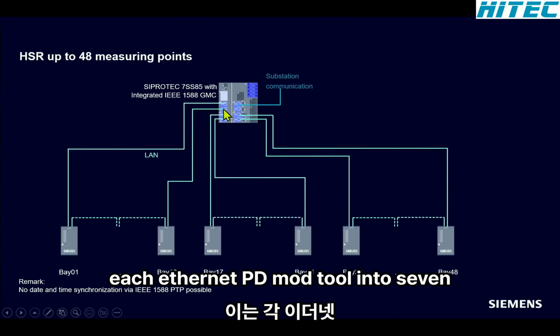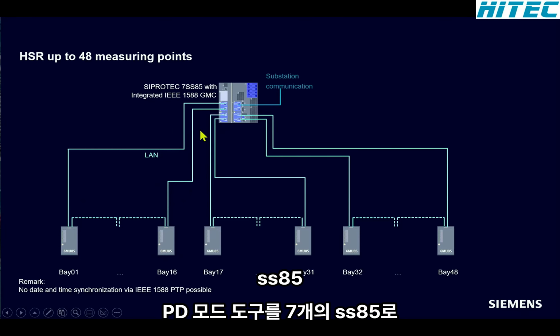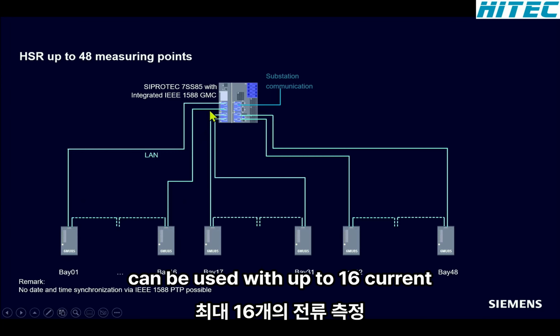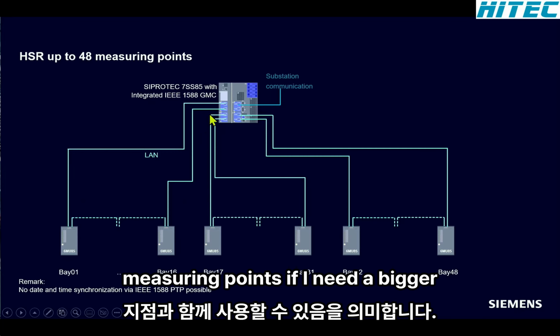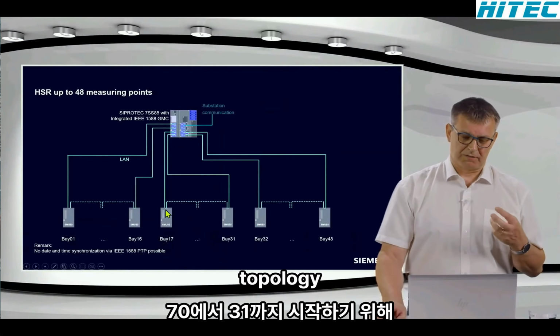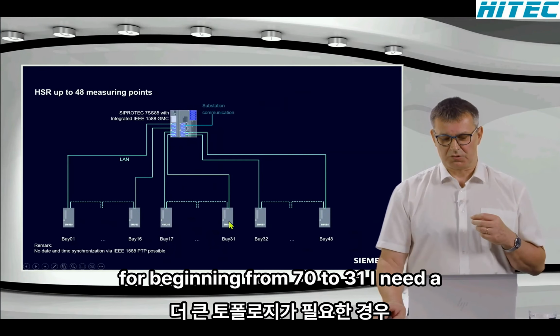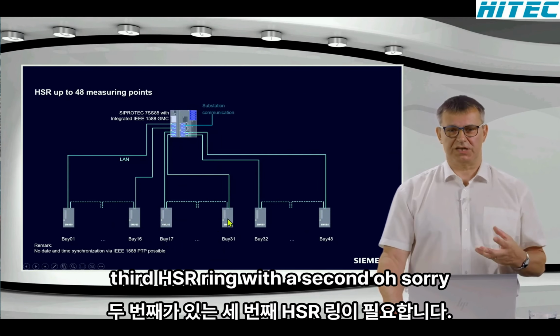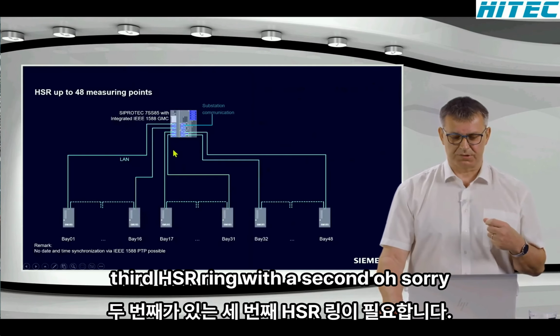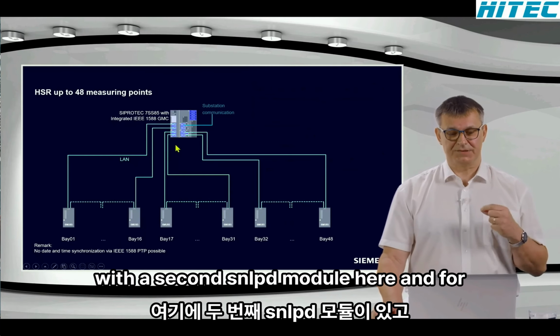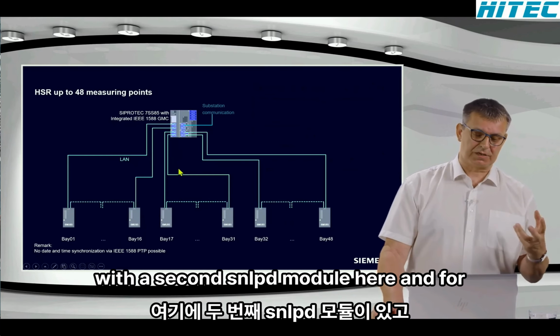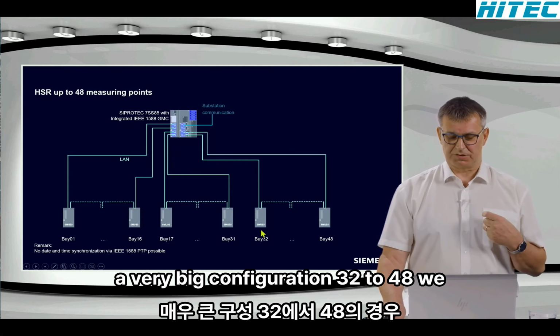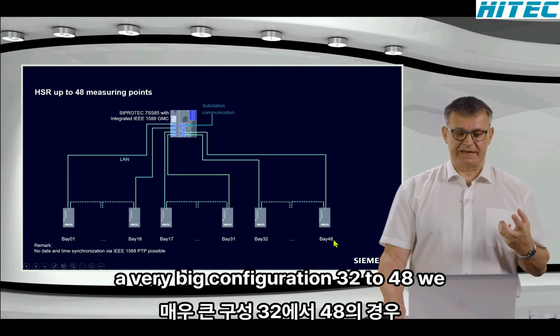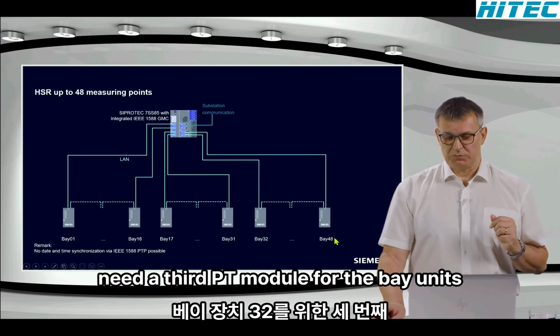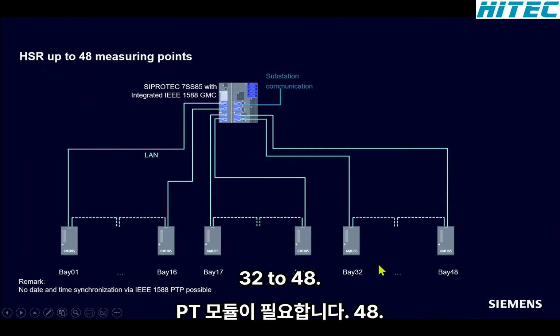That means each Ethernet PD module in the 7SS85 can be used with up to 16 current measuring points. If I need a bigger topology, beginning from 17 to 32, I need a second HSR ring with a second Ethernet module here. And for a very big configuration, 33 to 48, we need a third module for the bay units 33 to 48.